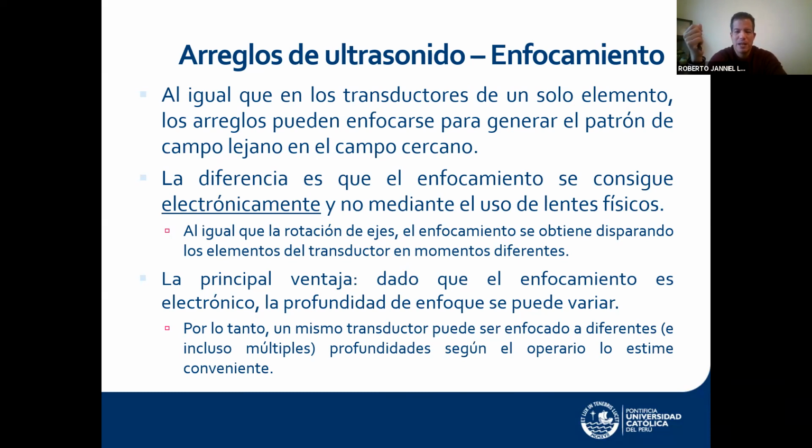Because if you want to create an image and you want to be focused at 2 or 3 different locations, you will have to first scan with the transducer of the first focus and throw it out, and then the other one, and throw it out, and then the other one. And by the way, that would imply actually moving the transducer, which in itself is a challenge, right? So it was not feasible, it was not practical.